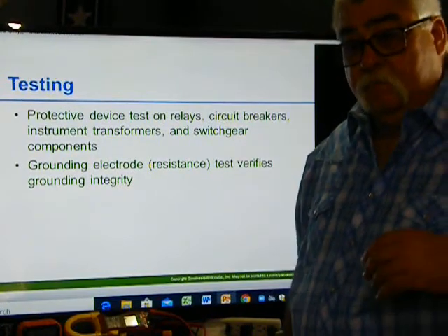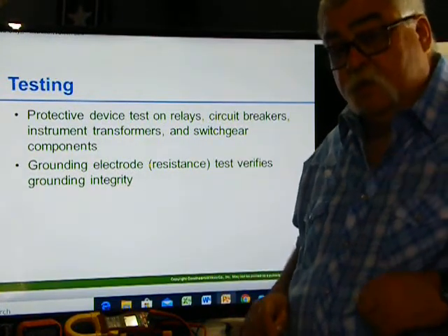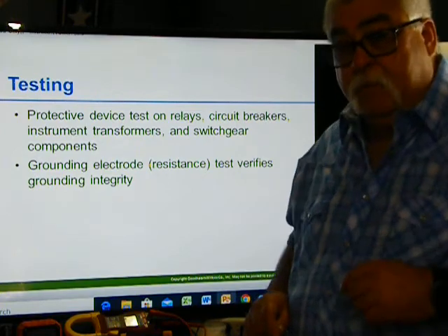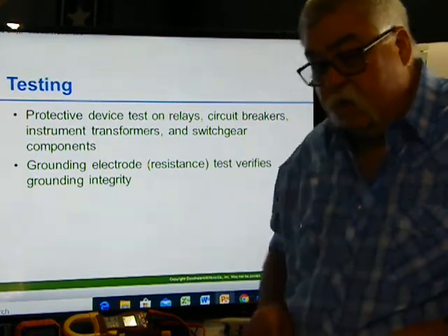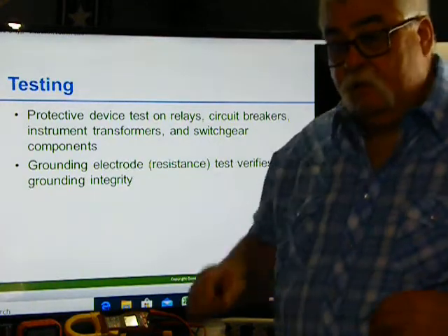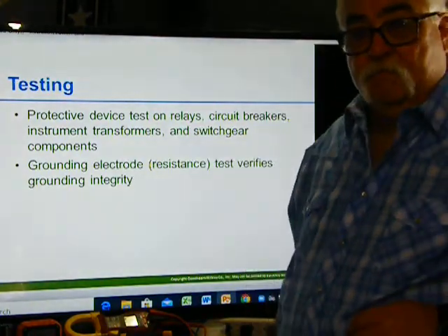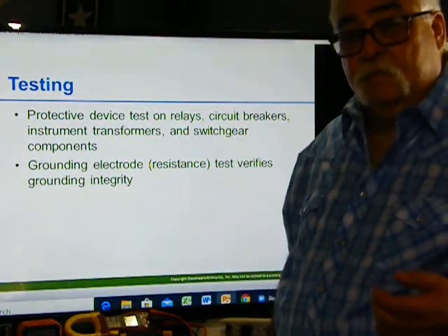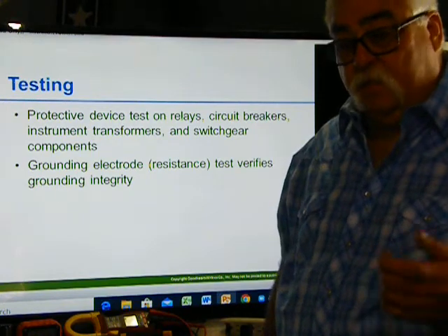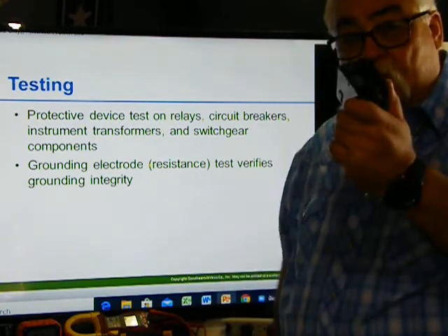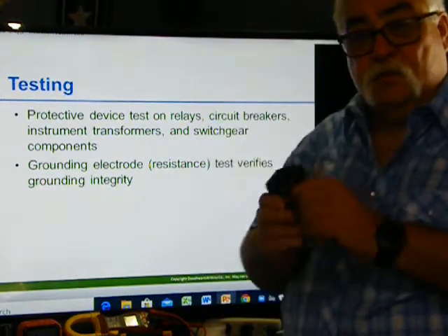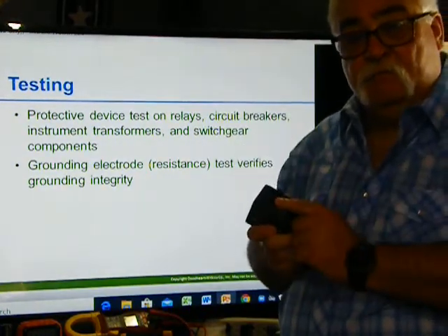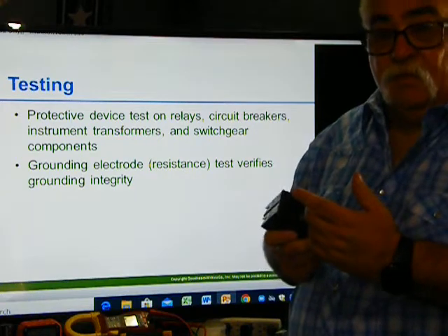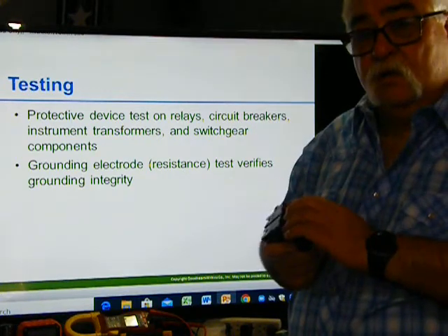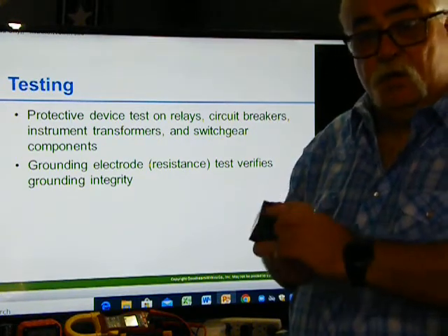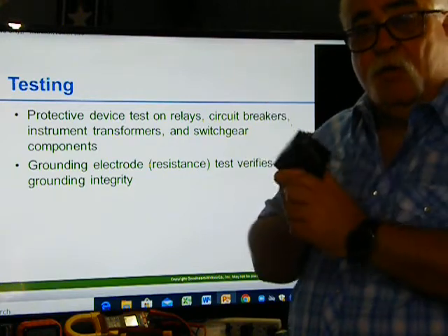So we'd come in and turn the generators on, put it in bypass, walk over to the big air breaker, hit the trip button, trip it out, then reset it. Okay, we were exercising the breakers. Okay, same thing with these. How many of you go exercise the breakers at your house? Okay, turn them on, turn them off. You don't have to do it, but you know, say that's something you should do at least once a year. Why? To exercise the breaker, make sure if it trips, that you can turn it back on again.